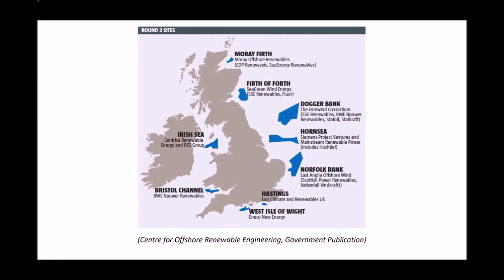Next we have our offshore wind farms, which are responsible for producing significant amounts of energy, and once again we see them surrounding the UK coastline. Note that the voltages produced at these wind farms would need to be stepped up to 400 kilovolts before being fed into the National Grid, and as discussed in earlier tutorials, that electricity also needs to be supplied at 50 Hertz.